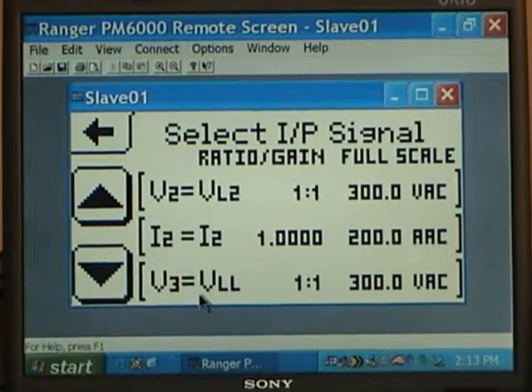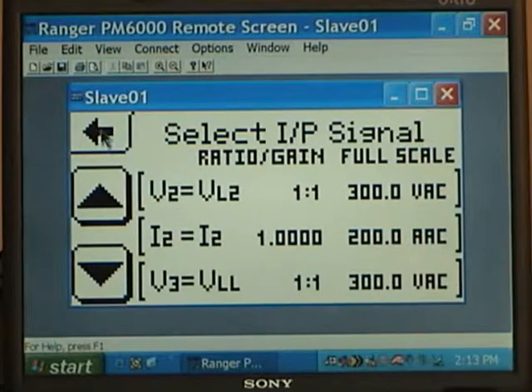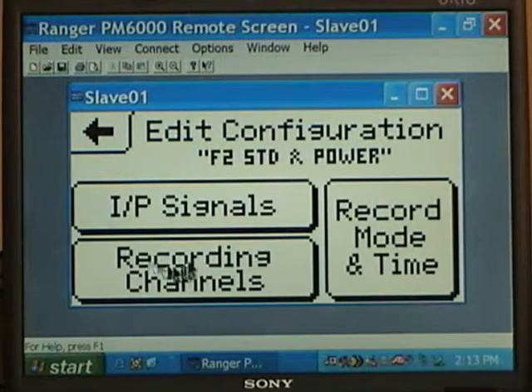And then here's voltage number 3, which is your L to L, which would be your line 1 to line 2, again at 0 to 300 volts. We do not compute it, we measure it. So any neutral problems will be picked up. And then that's our input signals.